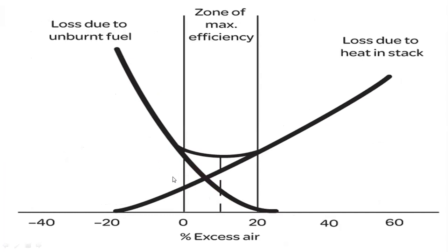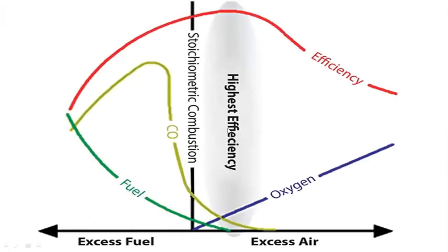When it comes to the zone of maximum efficiency, you always require 20% more than the stoichiometric requirement of oxygen or air, which we normally call excess air. Air-to-fuel ratio is normally 14:1, so for every kg of carbon you need to give 14 kg of air. You also have a stoichiometric requirement; beyond that you need to give a minimum of around 10% and a maximum zone of efficiency tolerable up to 20%. Loss due to unburnt fuel will be more in the region of less air, and if there is more air, you have a loss due to heat in the stack. Both extremes are not desirable. The zone of maximum efficiency — the combustion efficiency zone — is around 10 to 20% excess air.